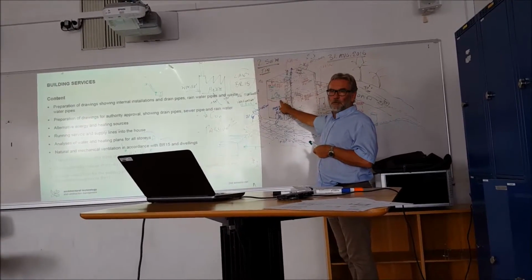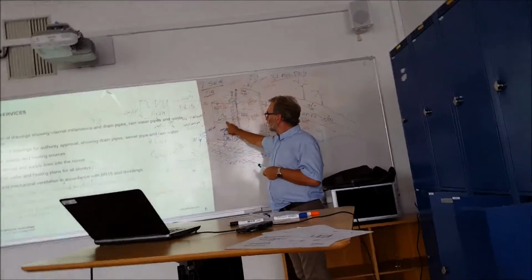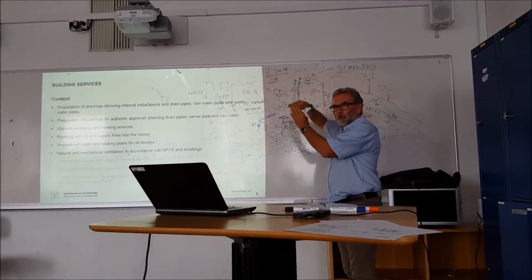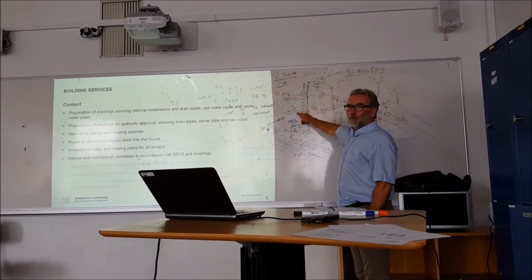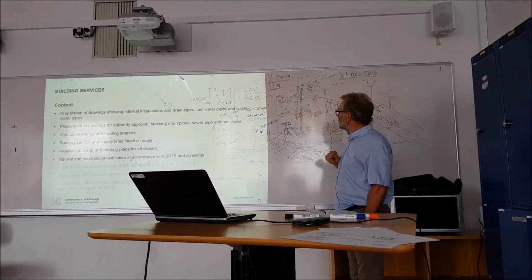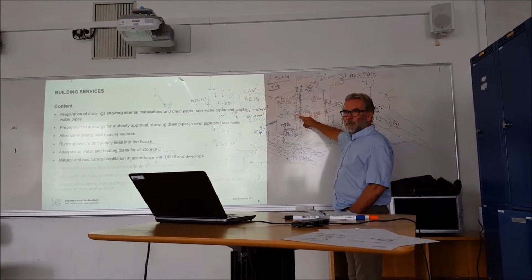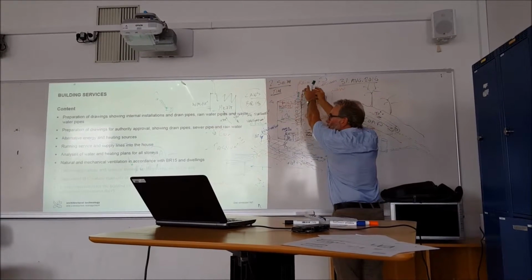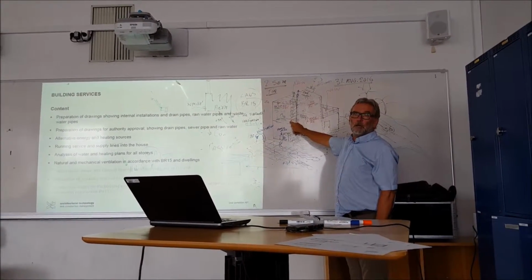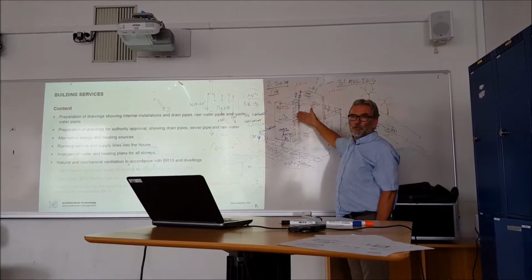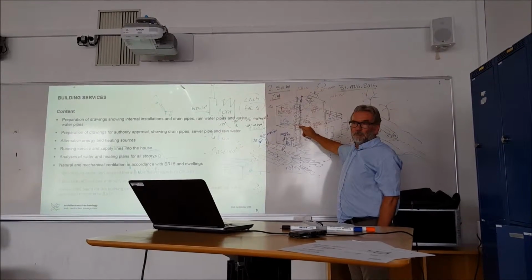So there's a need for you guys to understand in your design, where are we putting the pipes? And that's why these Posi-Joists, remember the ones with the holes, are ideal here, so that the pipes can go across, parallel to the joist, go through the holes and get into the shaft. But what do you do here with the shaft? If you've got a shaft that's coming all the way up and down through here, the shaft's going to probably be bigger than the centre to centre of your joists. So you're going to have to leave an opening here in your drawings and your design for the shaft.